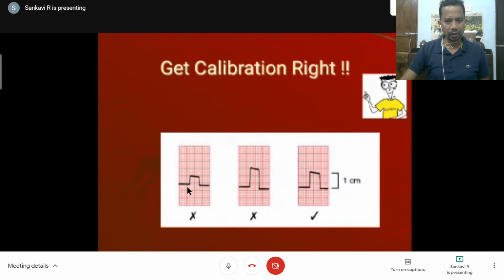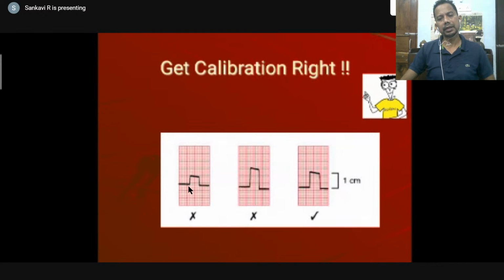Now, calibration is 10 small squares in height. There has to be a horizontal plateau and a vertical fall. So it has to go like this, like this, like this. If the machine is showing a calibration like this, it might form a false R wave, and your whole interpretation of the ECG will change. If the machine is showing it like this, it might form a Q wave or an abnormally deep S wave. And it has to be 10 small squares in height.